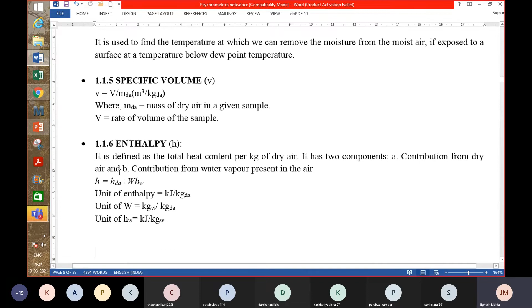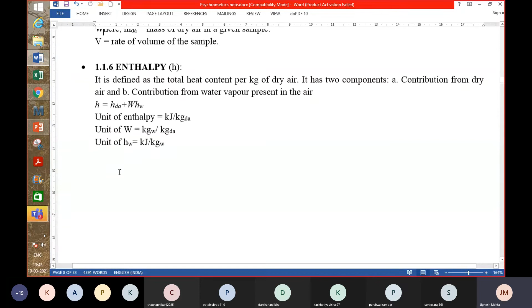And that's how you will calculate or use the formula for enthalpy, right? So HDA is nothing but Cp of air into temperature of air, and this part HW is nothing but 2501 plus Cp of water vapor multiplied by the temperature in degrees Celsius, right? So when you say 30, it is 30 minus 0, so it is 30. So that's how you will be finding the total enthalpy content of the air, which is a very important property in psychrometrics.